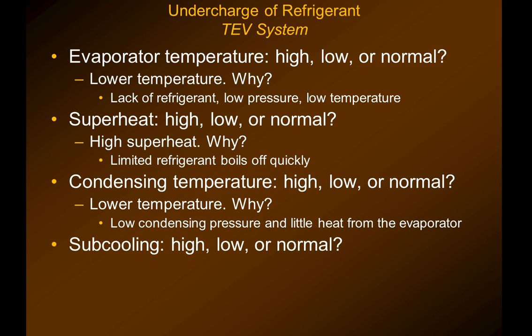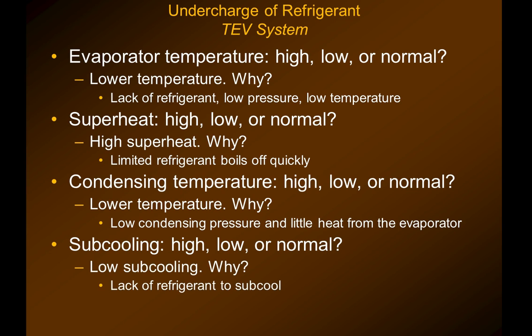And is the subcooling going to be high, low, or normal? It's going to have low subcooling. Again, that is because there's a lack of refrigerant to subcool.